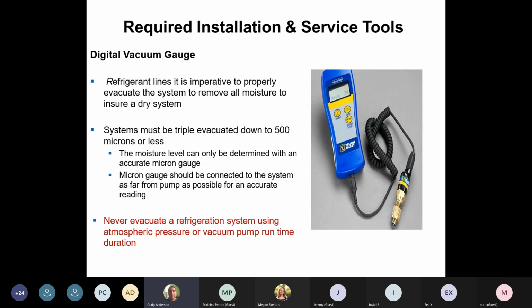Watching your gauge, leaving the vacuum pump on for a half an hour, 20 minutes, that's not telling us if the moisture's out of the system. The only way to do it is with a digital vacuum gauge. All kinds of people make them, Yellow Jacket, UEI, anywhere. Make sure you have one. It's the only way to determine time, and looking at your gauges is not going to do that.